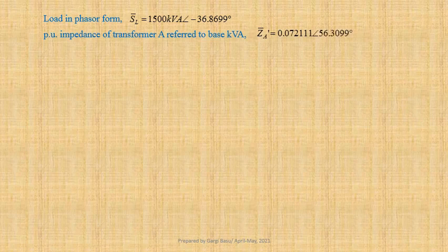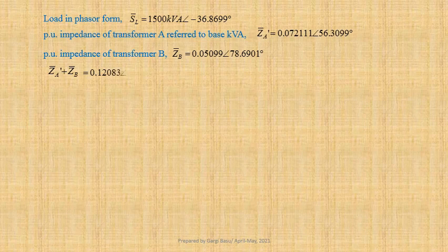Load in phasor form, SL equals 1500 kilovolt ampere at an angle minus 36.8699 degree. Per unit impedance of transformer A referred to base kVA, ZA dash equals 0.072111 at an angle 56.3099 degree. Per unit impedance of transformer B, ZB equals 0.05099 at an angle 78.6901 degree. We have calculated ZA dash plus ZB equals 0.12083 at an angle 65.556 degree. Let us now determine the load shared by transformer A.